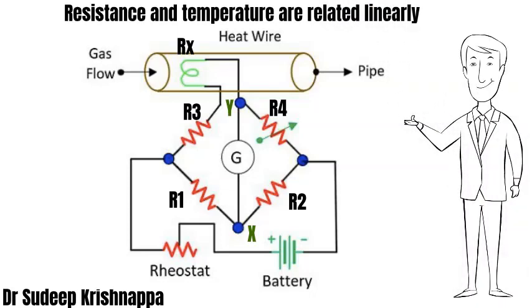When the bridge is balanced, there is no potential difference across points X and Y, so a voltmeter placed at position G would not record any deflection. In this system, R1 and R2 are known and fixed; R4 is known and can also be altered. A heating element placed in the path of gas flow will have a resistance Rx, which is determined by the temperature of the heating element. The sum of R3 and Rx represents the total resistance at position R3.